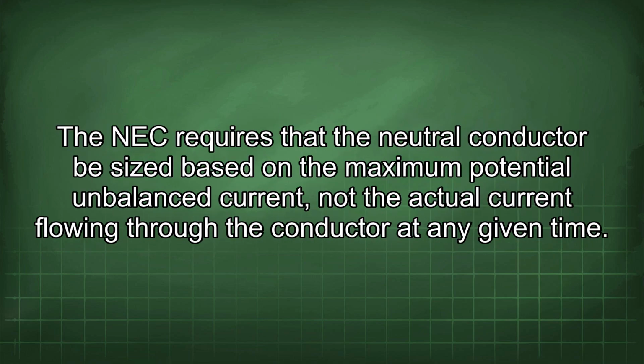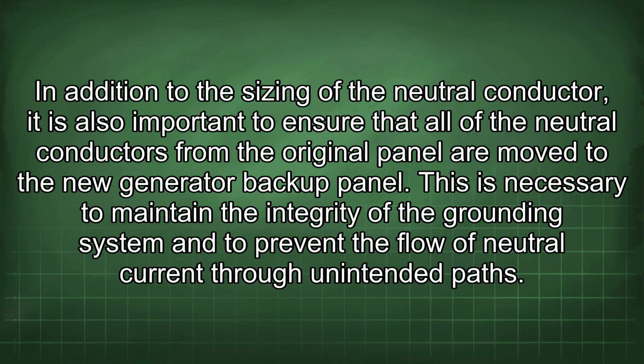The NEC requires that the neutral conductor be sized based on the maximum potential unbalanced current, not the actual current flowing through the conductor at any given time. In addition to the sizing of the neutral conductor, it is also important to ensure that all of the neutral conductors from the original panel are moved to the new generator backup panel.